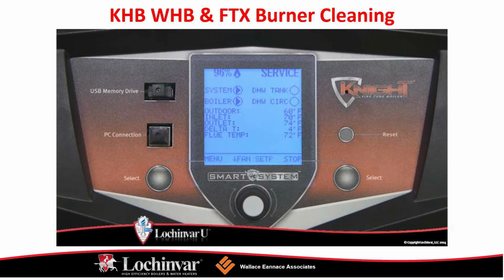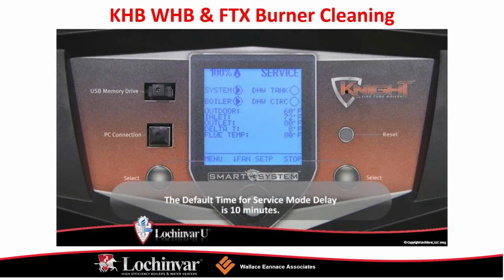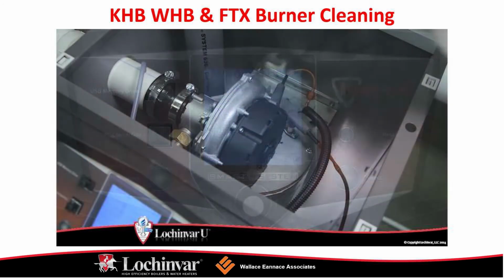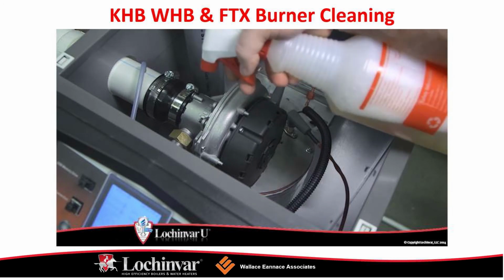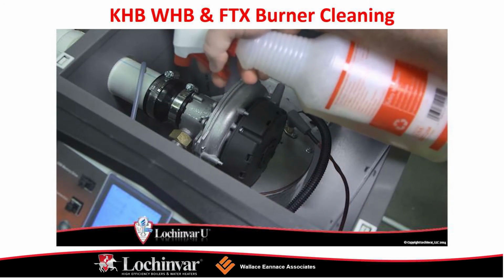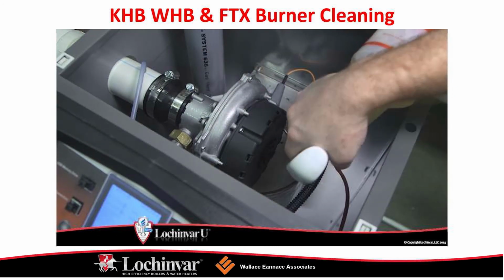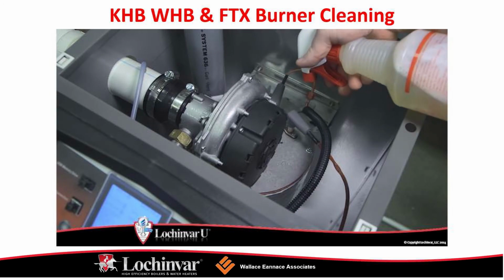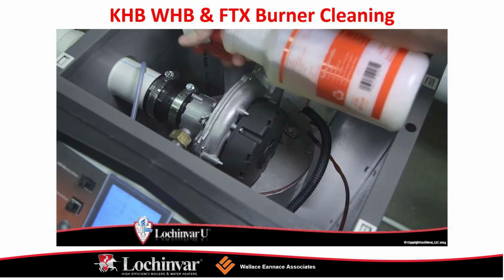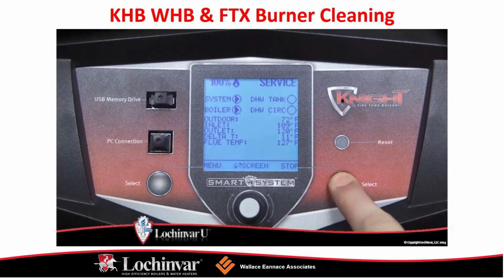Reconnect the wiring from the flame rod, spark igniter, and ground terminals to the heat exchanger door, and reconnect the two wiring harness connections to the combustion blower. Now replace the bezel to the front of the unit and install and tighten the 4 screws securing the bezel. Now reconnect the ribbon cable from the display to the main control board.